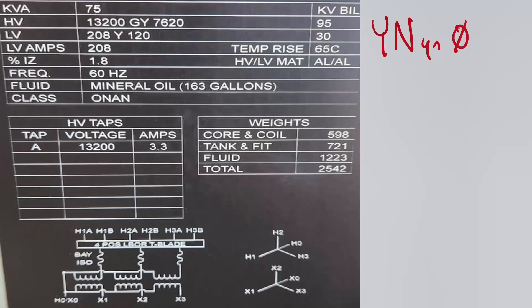So you need to be looking at A phase on both, or B phase on both. So right now, what we're going to leverage is the fact that B phase on the primary is already at 12 o'clock. So where is B phase on the secondary? Well, that's at 12 o'clock also. Now we don't need to label this as a Y,N,12 or a zero. It doesn't matter. We don't need to do that because we're always, by default, going to assign the primary at 12. So if we assign the primary at 12, the secondary is a Y,N because the neutral is brought out, like we said. And the clock shift from primary to secondary is zero degrees because they're both at 12 o'clock. So that's how this is done.